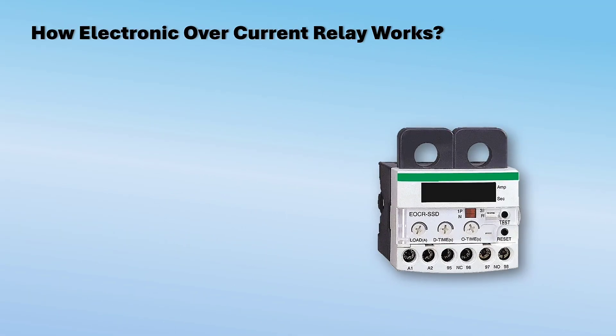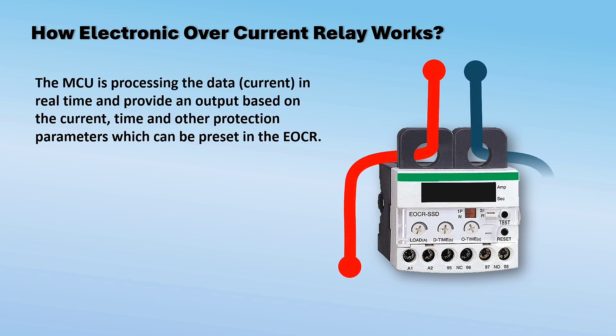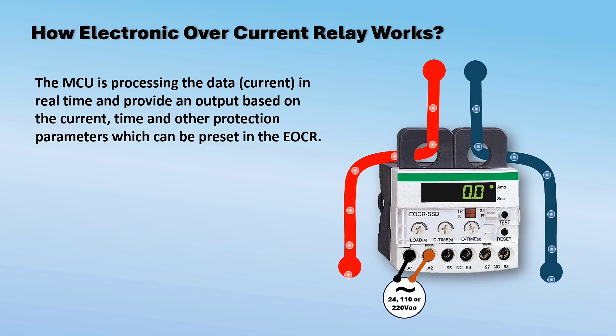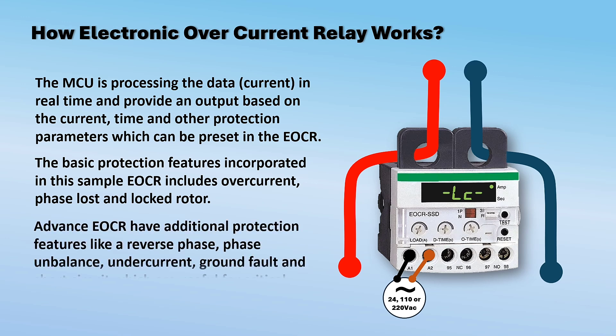How the electronic overcurrent relay works: the MCU processes the current as data in real time and provides an output based on the current, time, and other protection parameters which can be preset in the EOCR. The basic protection features incorporated in this sample EOCR include overcurrent, phase loss, and locked rotor. Advanced EOCRs have additional protection features like reverse phase, phase unbalance, undercurrent, ground fault, and short circuit, which are useful for critical equipment.